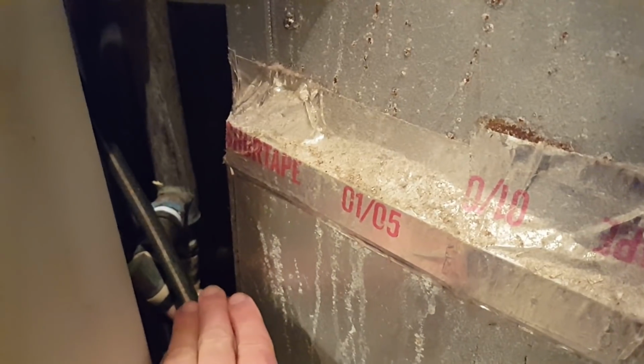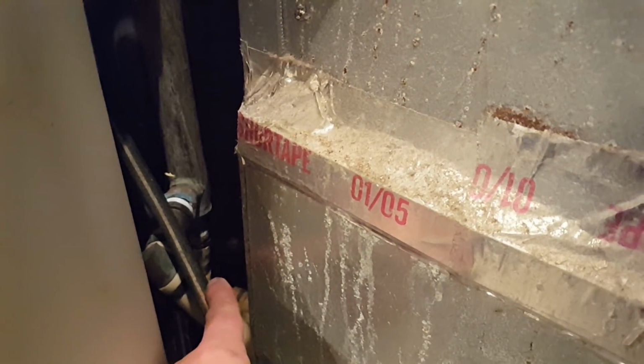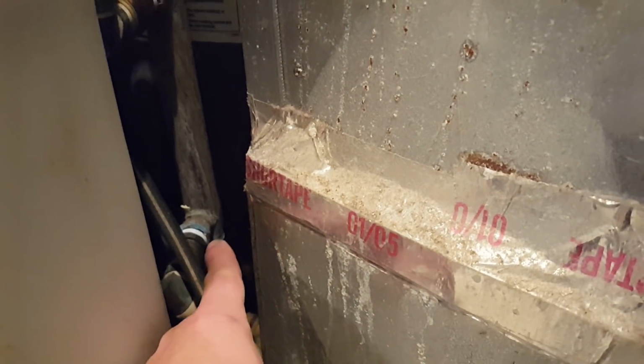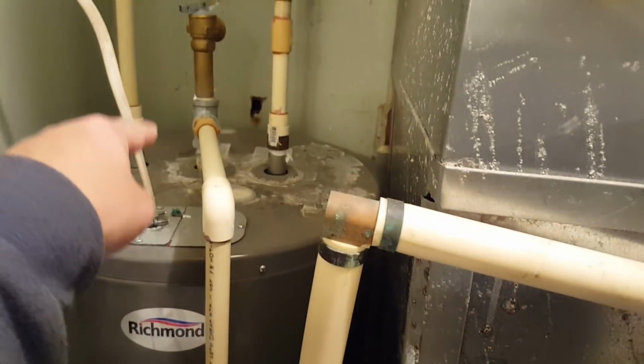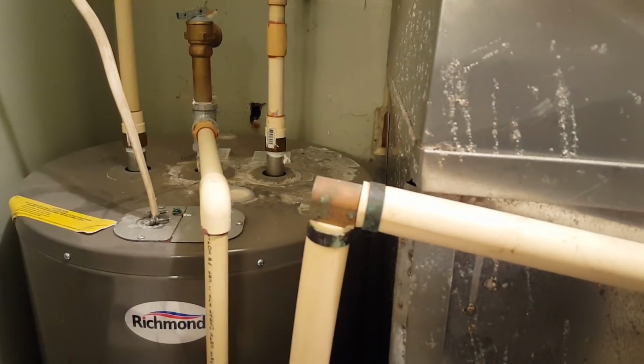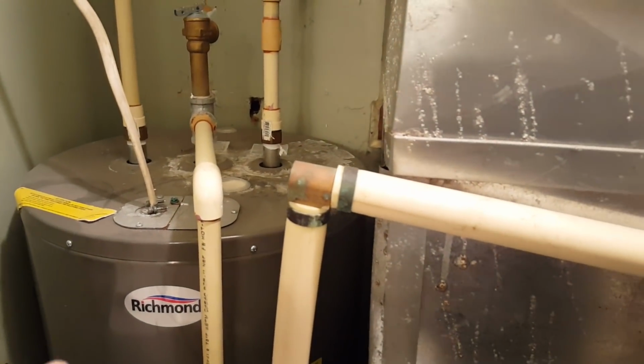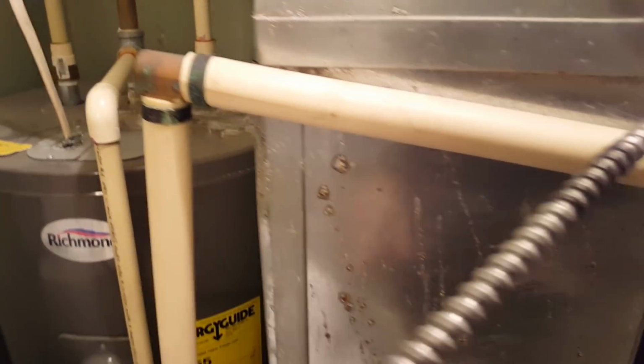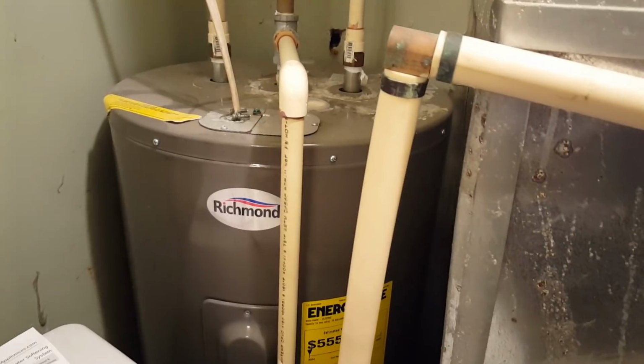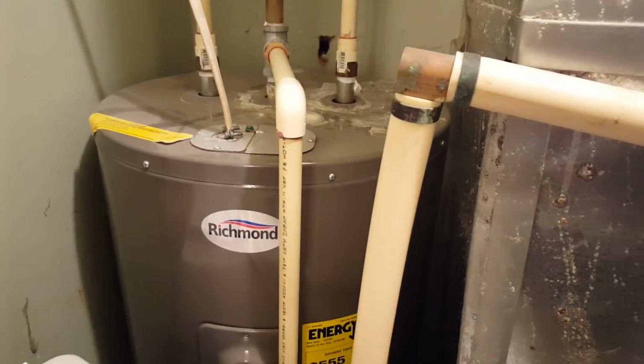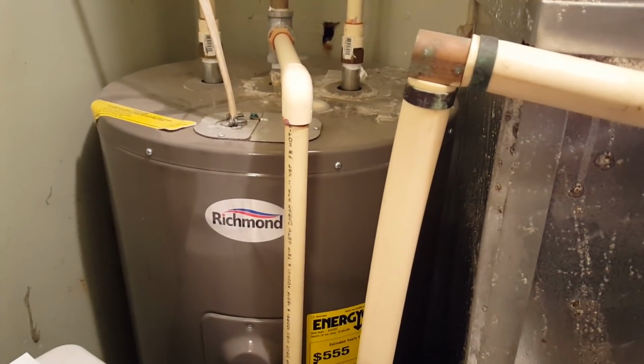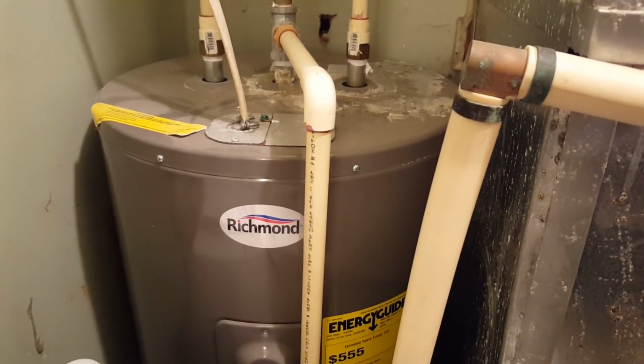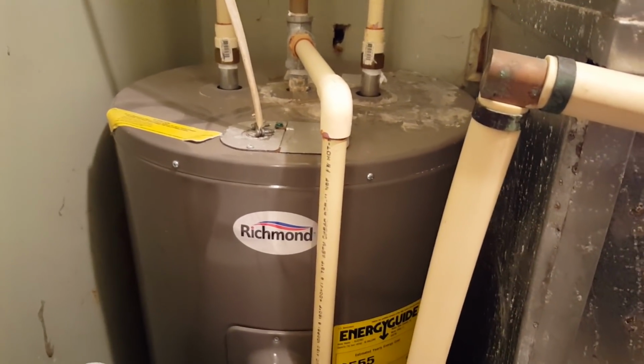So the cooler water that settles at the bottom of the hot water tank kind of thermal siphons through here, gets heated, and goes up through this pipe, then dumps into the top of the hot water tank. As it cools down again, it thermal siphons through and gets heated again. So there's no mixing of the outside boiler water with our fresh or hot water here, but it heats it through that thermal siphon. This could be adapted to any hot water tank.